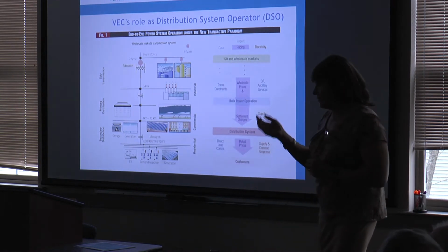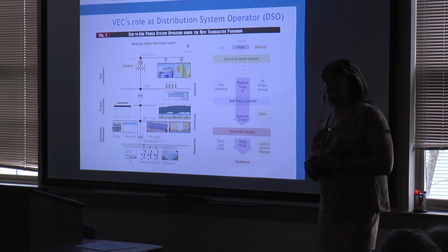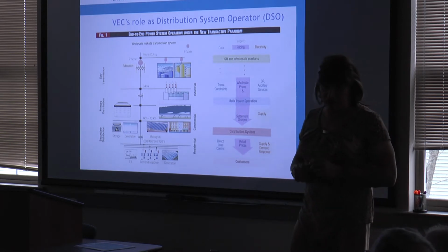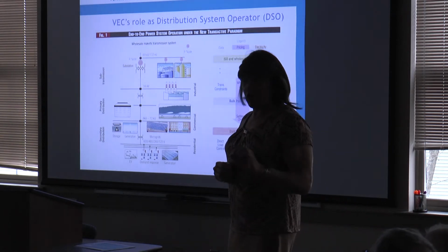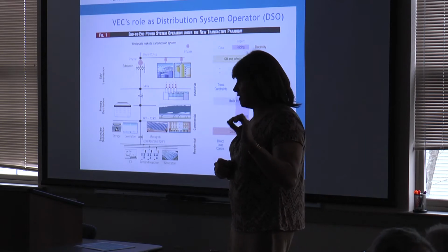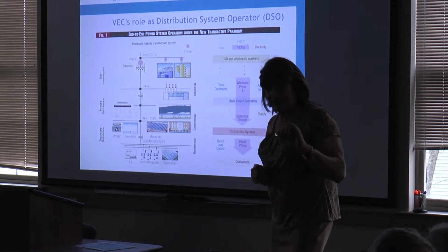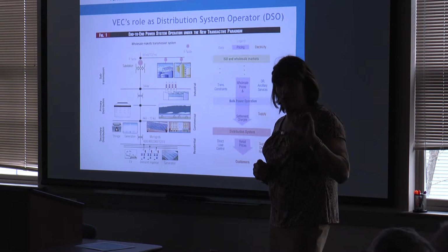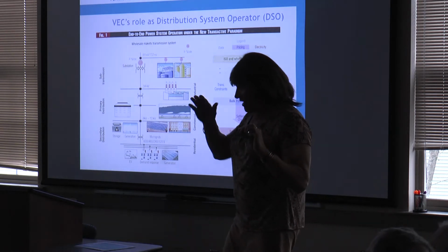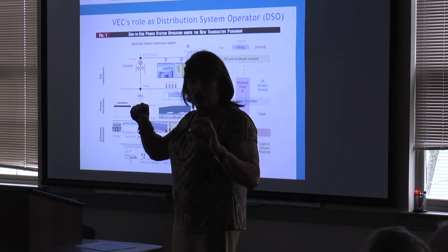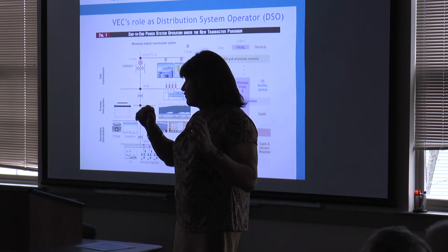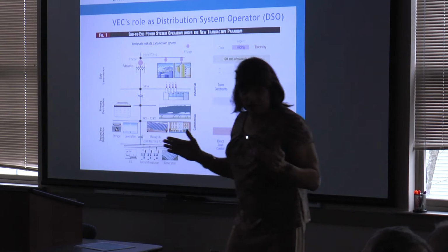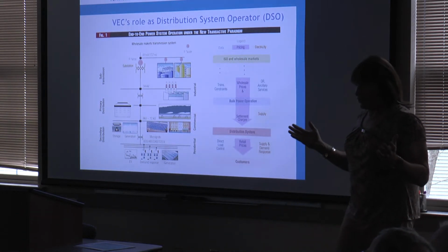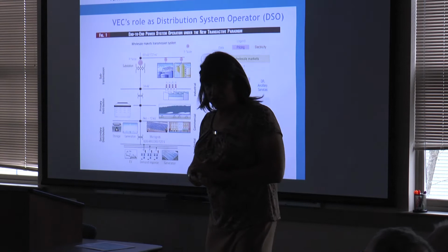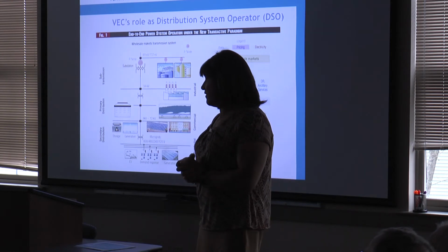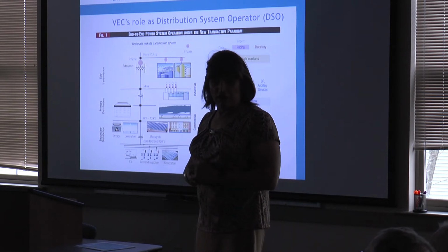So there's a whole bunch of cautionary indicators that ISO New England looks at. And they make sure there's reserve spinning generation on the grid at all times, so that in case something happens, there's enough spare power to keep that water level stable. Because the grid can collapse in 3 or 4 cycles of a sine wave, which is like 50 milliseconds. So within a tenth of a second, you can get a grid collapse. So it's very important that we have enough spinning reserve.